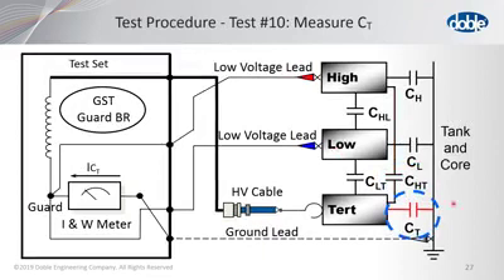And we get CT. We get the CT insulation only. Notice if you follow the circuit, you'll only measure what's going through the ground lead. Remember, the ground lead is a measurement lead. It should be connected right on the tank. Okay. Now, any other insulation is guarded away. Notice it's guarded away and is not measured.